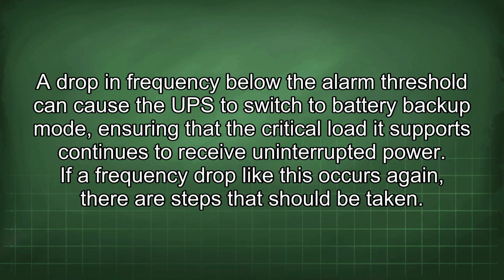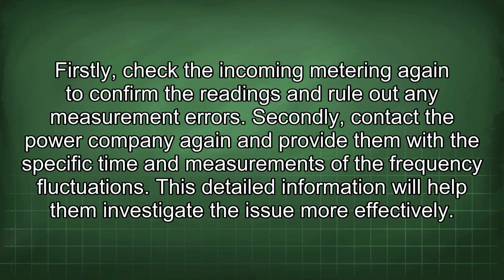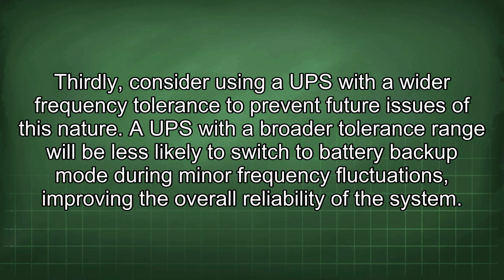If a frequency drop like this occurs again, there are steps that should be taken. Firstly, check the incoming metering again to confirm the readings and rule out any measurement errors. Secondly, contact the power company again and provide them with the specific time and measurements of the frequency fluctuations. This detailed information will help them investigate the issue more effectively. Thirdly, consider using a UPS with a wider frequency tolerance to prevent future issues of this nature. A UPS with a broader tolerance range will be less likely to switch to battery backup mode during minor frequency fluctuations, improving the overall reliability of the system.